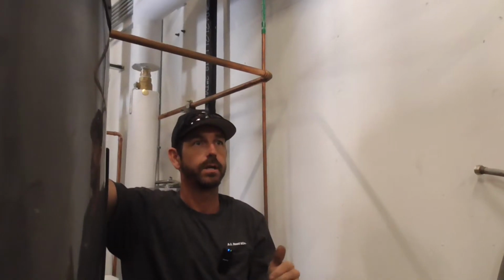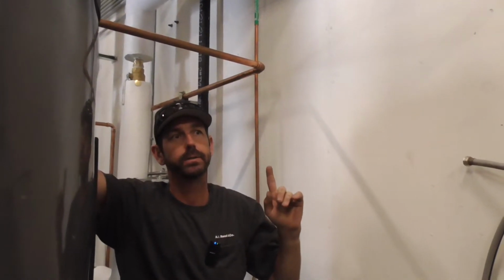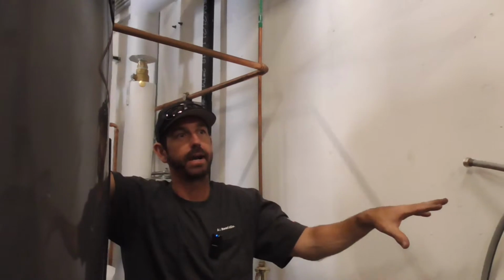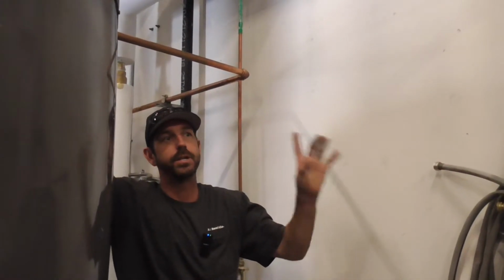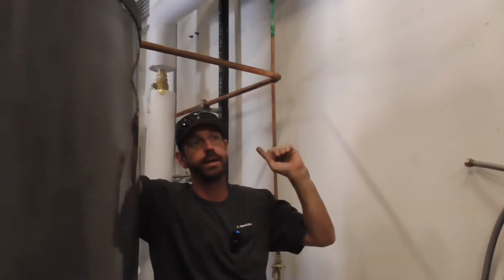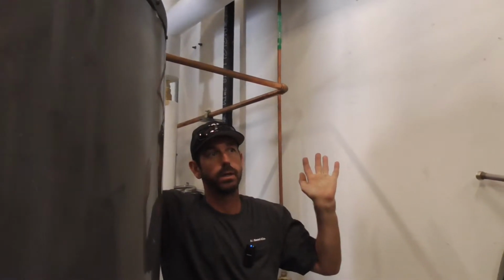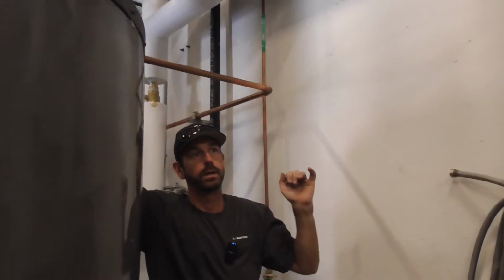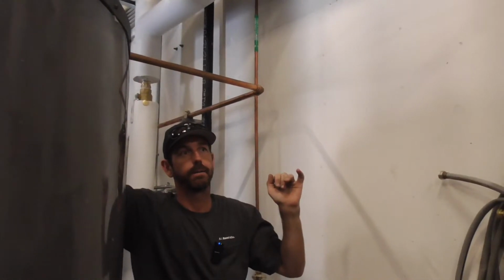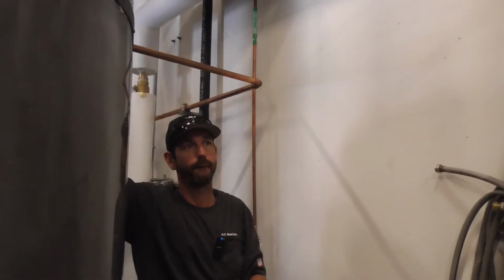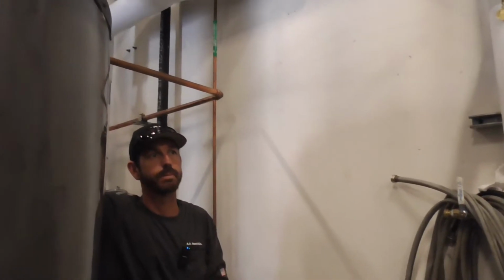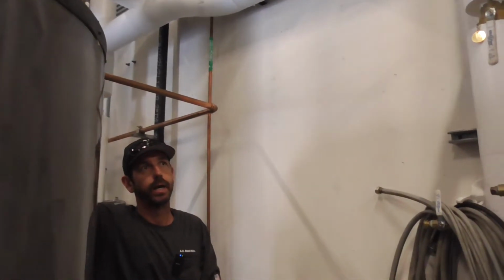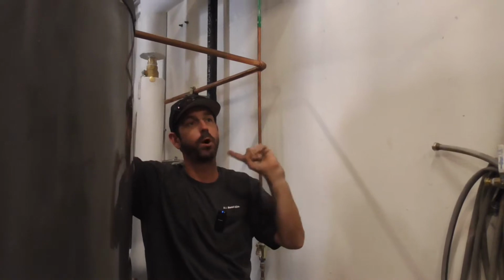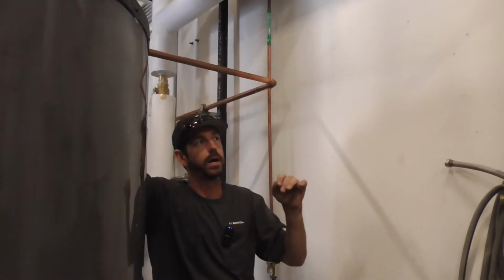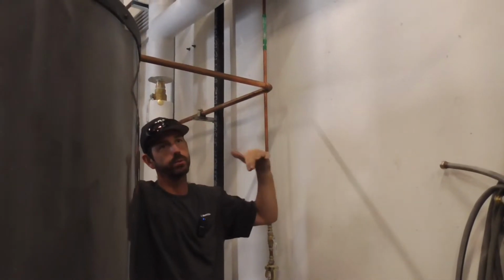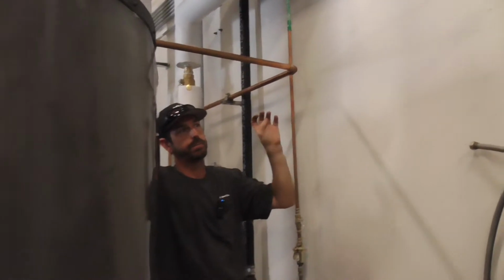Does that make sense? Have you guys had to deal with this part before? Nope. Okay, so do you have mixing valves other places? And there's not this split between this, or we just never looked at? I'm just wondering. No, it's just water in through the mixing valve and then water out to the building. Okay. And then there is a return with a circ pump on it that just loops back, bypassing the storage tank? It would depend how the building's piped. If it's one pass, you probably don't need all this. We do have multiple sources, but again, just depending.